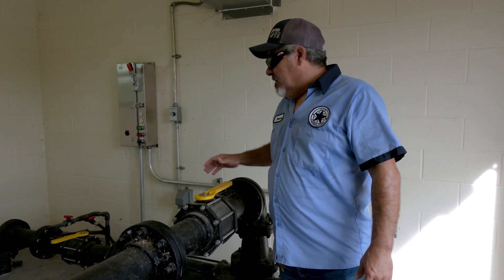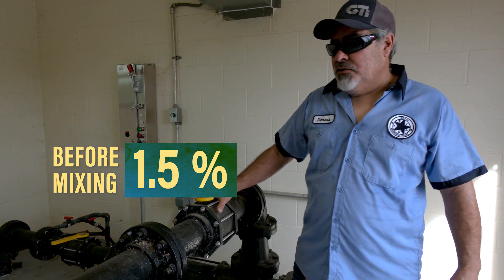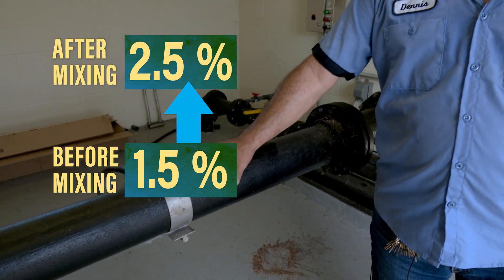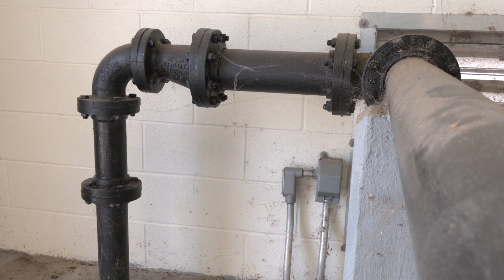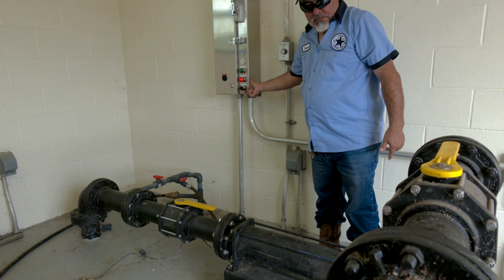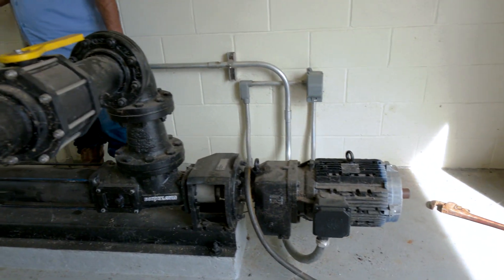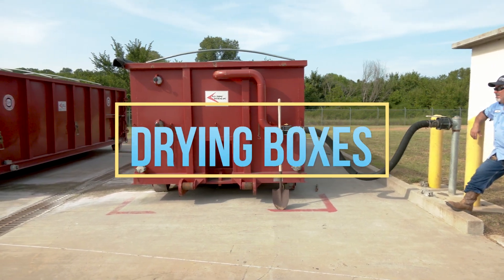Our waste activated sludge comes through here at about one and a half percent. When it mixes with the polymer and water it hits about two and a half percent. From here it pumps into our drying boxes. This is an indoor facility so we do have heat in here. If you're outdoors you do need heat trace insulation. Our next step is the drying boxes.